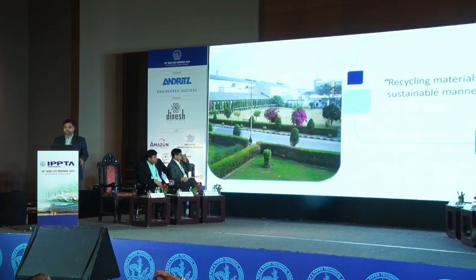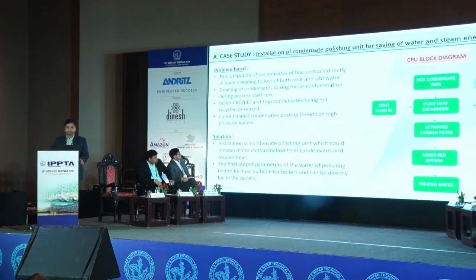Coming to the second step, recycling materials in a sustainable manner. Here is a case study of installing a condensate polishing unit for saving water and steam energy. The problem we faced was non-utilization of a few sections' condensates directly in our boilers, draining of condensates during minor startups, and contaminations. Boiler CBD, IBD, and trap condensate also cannot be directly utilized in the boilers. Contaminated condensates pose a threat to the high pressure boiler. The boiler life is directly affected by the quality of water we input.